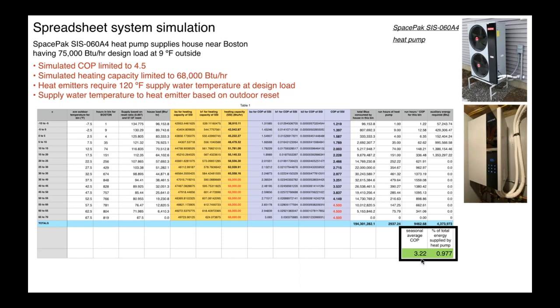And the bottom line is this, two things. Our seasonal average COP, where we look at the COP within each temperature range and the number of hours, we multiply those together, add it all up, and then divide by the total number of hours. So it's a time-weighted average COP, 3.2. That's actually a pretty good figure. And it compares favorably to what some geothermal systems would produce in a similar climate with a similar water temperature requirement and so forth.